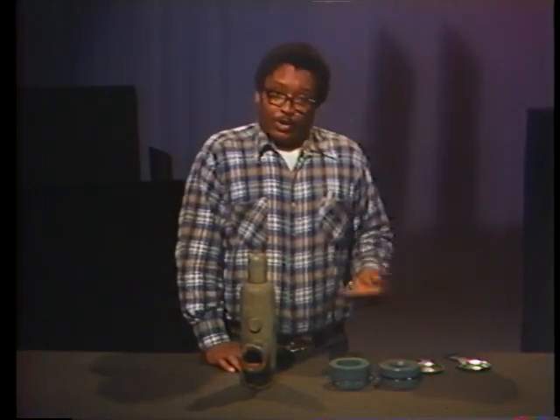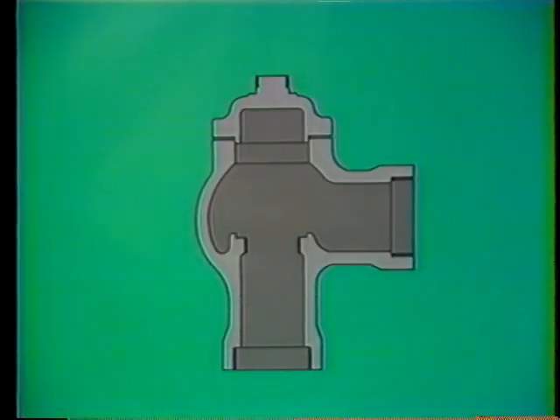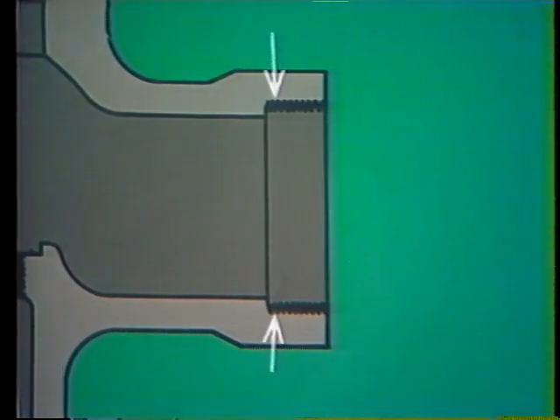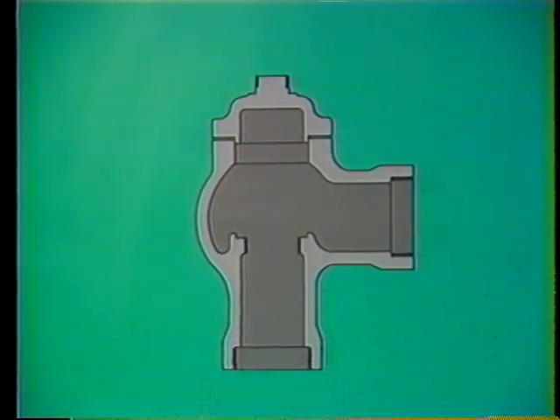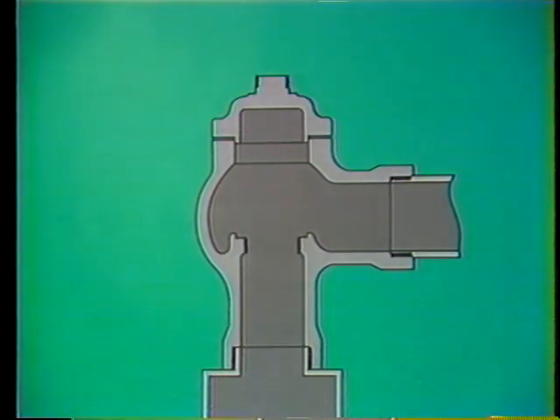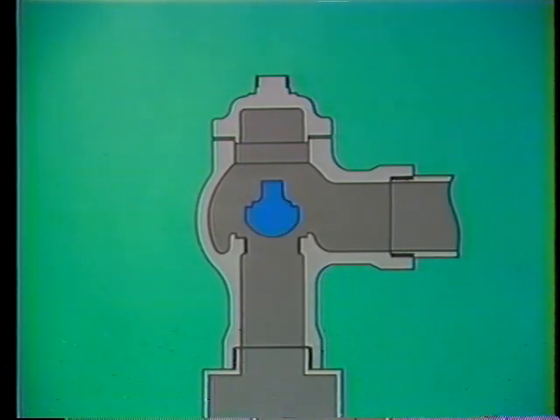The outer shell is called the valve body or valve casing. It gives over-pressurized liquids a path to flow through, as well as holding the internal parts of the valve in their proper position. A look inside the valve body shows the inlet and the outlet. On this particular valve, the inlet and outlet are both threaded. The threads enable the inlet to be connected to the system and the outlet to be connected to discharge piping. When system pressure is normal, the path from the inlet to the outlet is blocked by the disc, also called the plug.